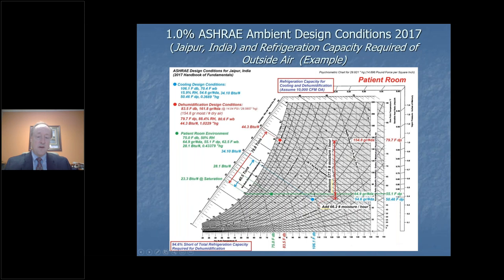And also, you'll see if I'm going from that peak dehumidification day, I would need to remove 577.9 pounds of moisture per hour to go from there to there. If I had only designed for that peak dry bulb day, I would actually need to add moisture from that case up to here in order to meet my load or my condition of 75/50. So that's a huge difference, and that's in a patient room.